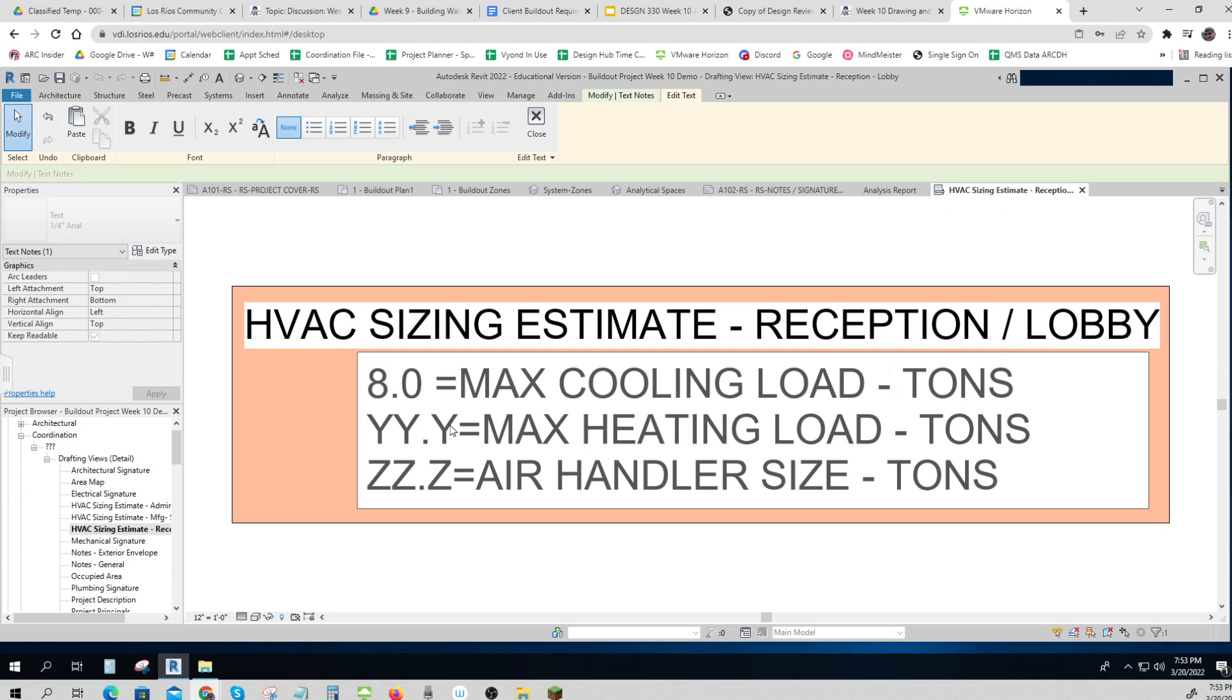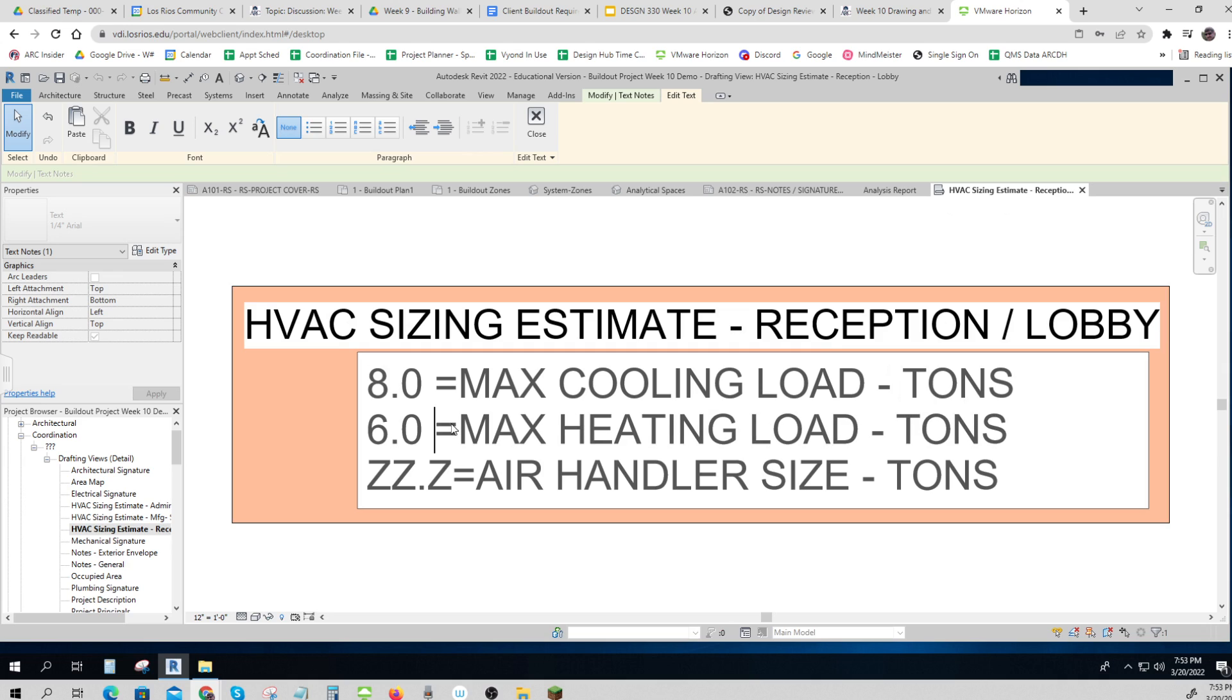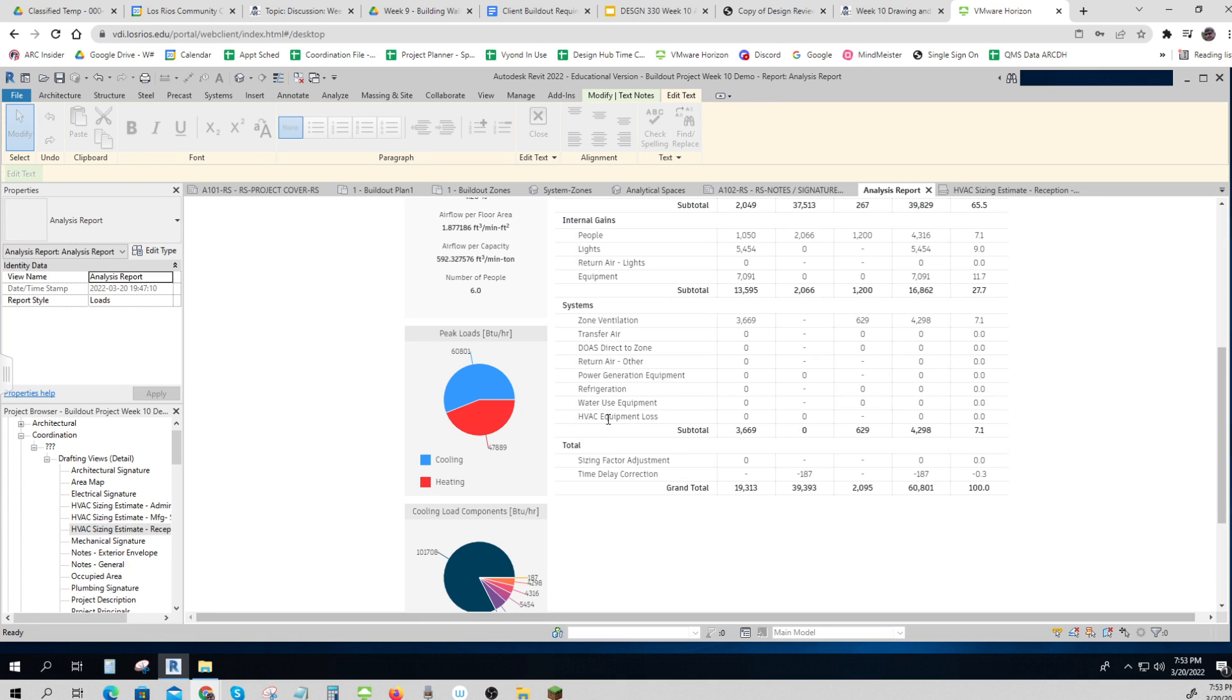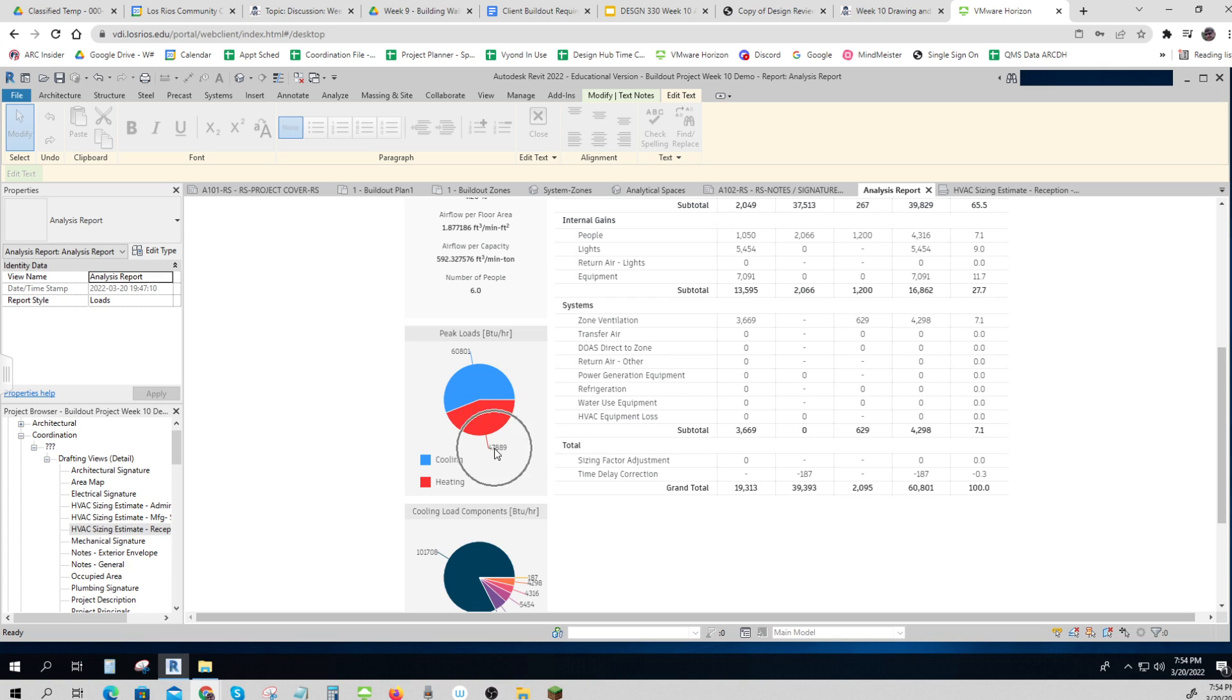And I would do the same calculation for heating. Let me say that that was 6.0. Yes, I'm putting numbers down, you have to calculate them. Get that number that you see in the analysis report. Blue is cooling, you have to read the number. Red is heating, you have to read the number. And then you have to kind of round it up to the next best one.